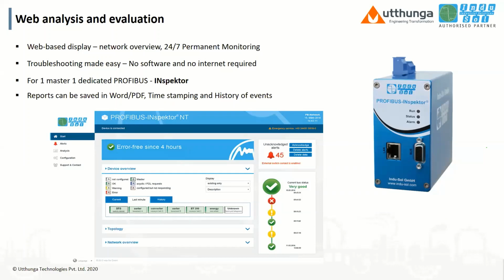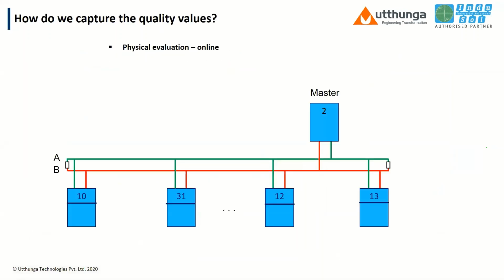So for one master, one dedicated inspector. Inspector will be acquiring complete information from the master itself in a passive mode. It is a passive data logger. No need of any interruption in the network. The female port of the controller will be connected with a D9 connector and will be taking reports through the LAN connection. So this is how we can pinpoint the error.